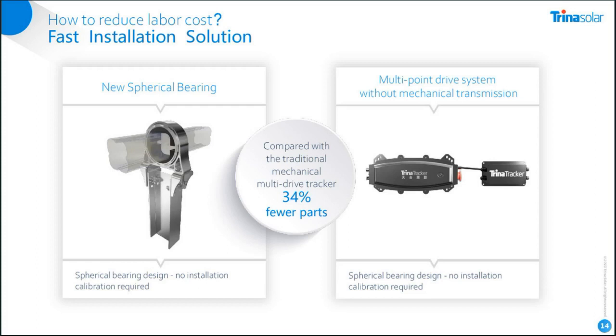And our R&D team also created an innovative multi-motor system. Compared with the traditional mechanical multi-drive system, it can reduce components by 34%. Because this multi-motor system has no transmission bar, no bar holder or bearing, we just need a main TCU and a slave TCU to control two different motors. That's enough. So firstly, it can reduce the labor cost because there are fewer components. Secondly, it can also avoid so many mechanical weak points.